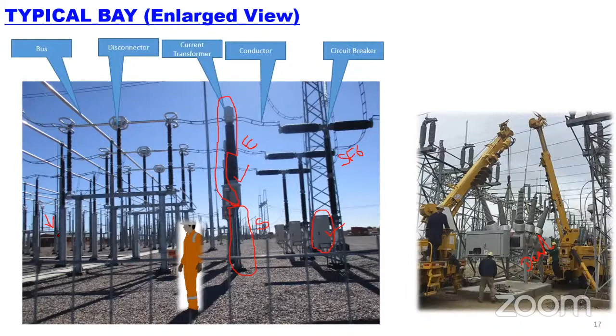And also what you can understand from this, in the circuit breaker, you can see there is an operating box. This operating box helps to receive all control cables from the control room. So from here, the control cables will travel through the cable trenches to the control room. So the control room you can see somewhere here on the back side of the structure. Okay. So this control cable helps to carry all the commands and signals from the circuit breaker, current transformer and the disconnectors, and will connect to your control system.